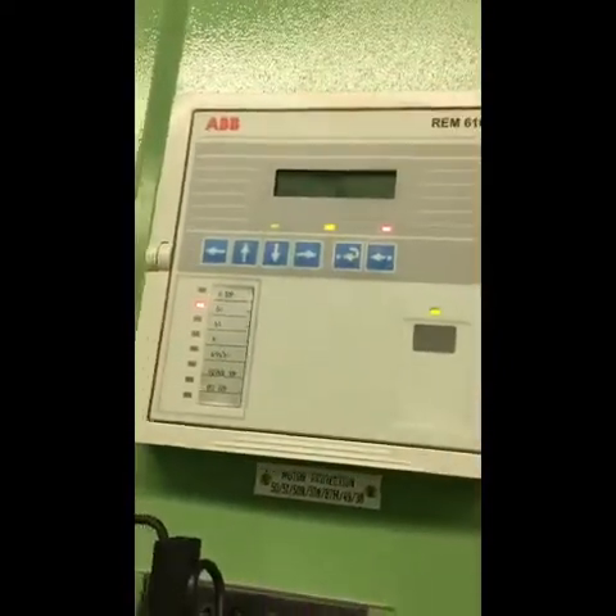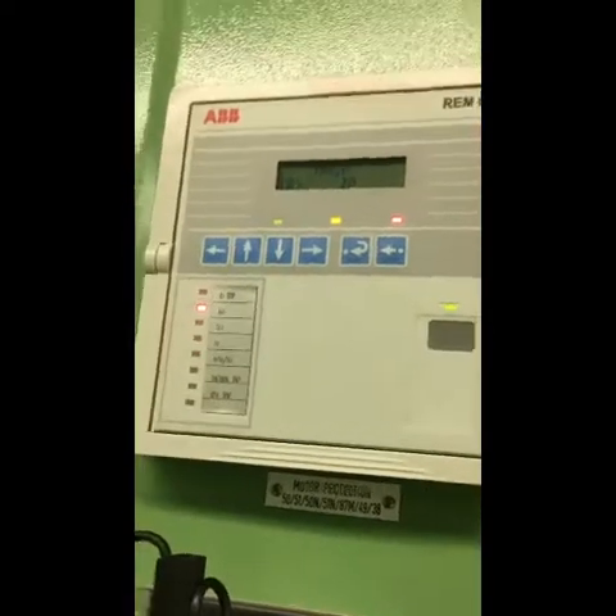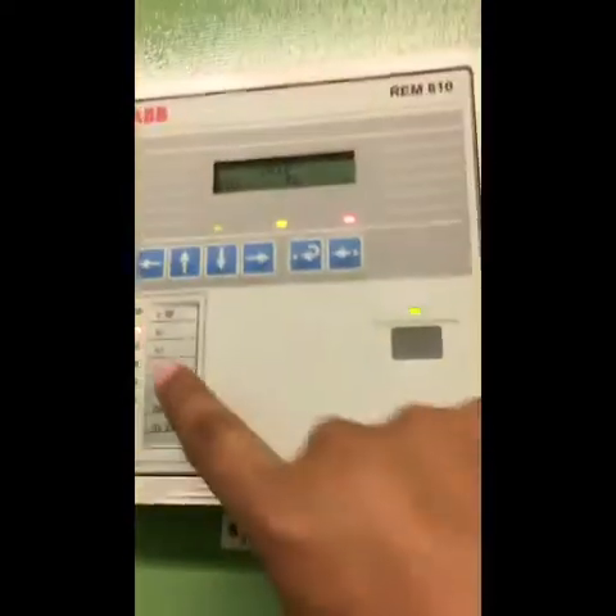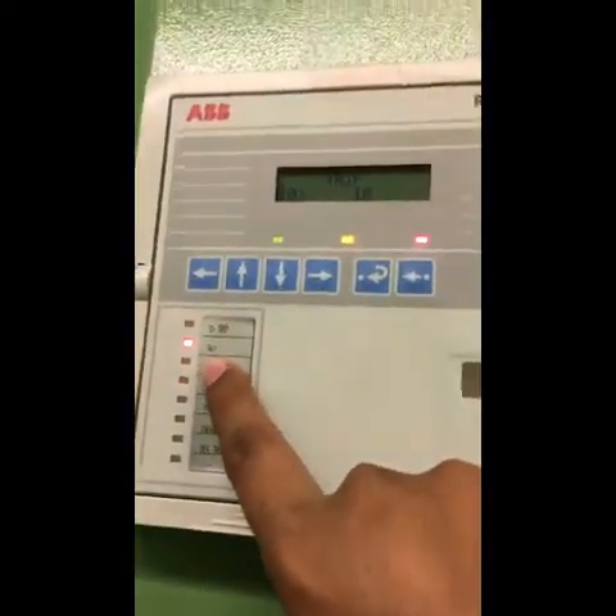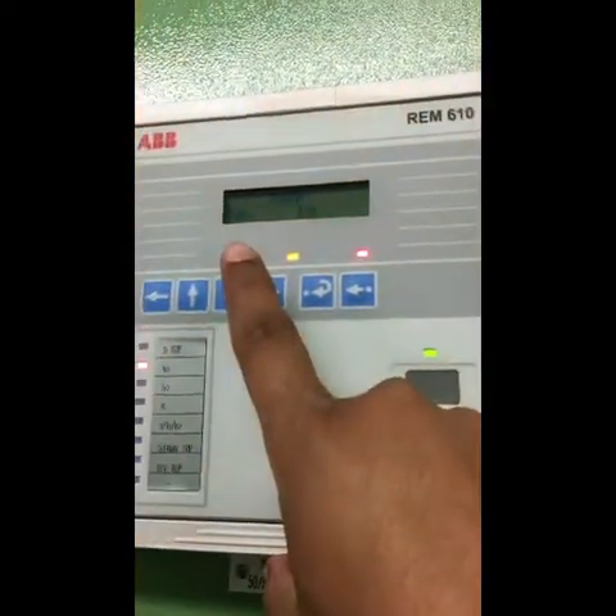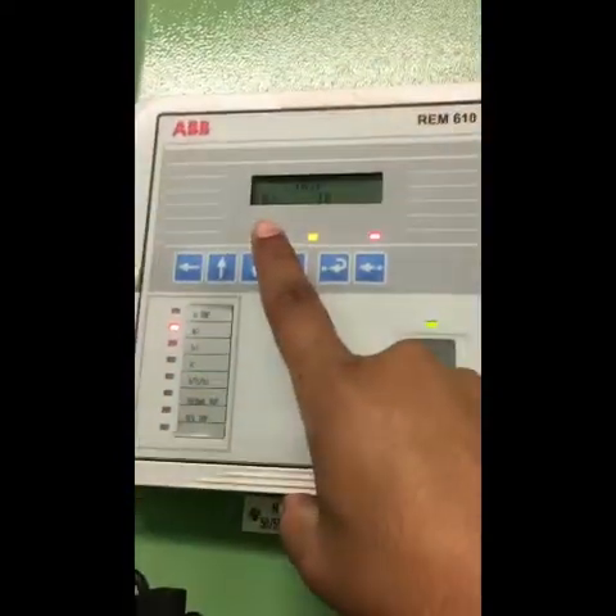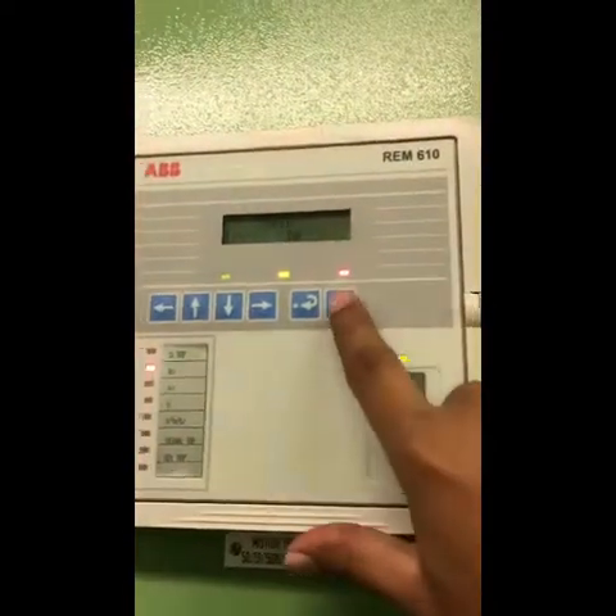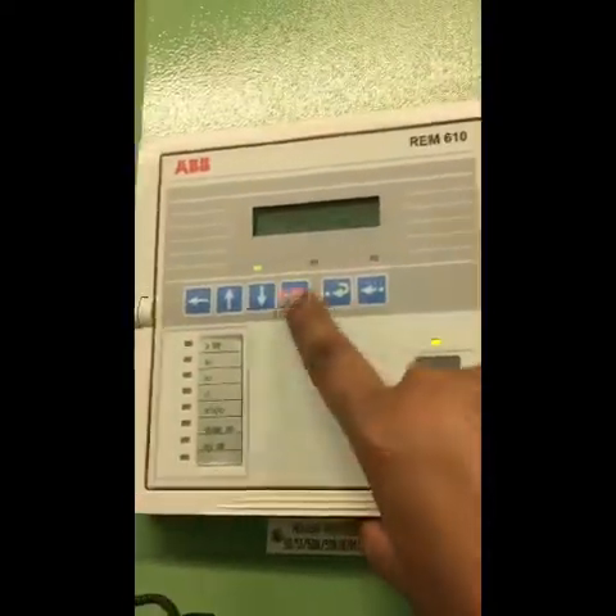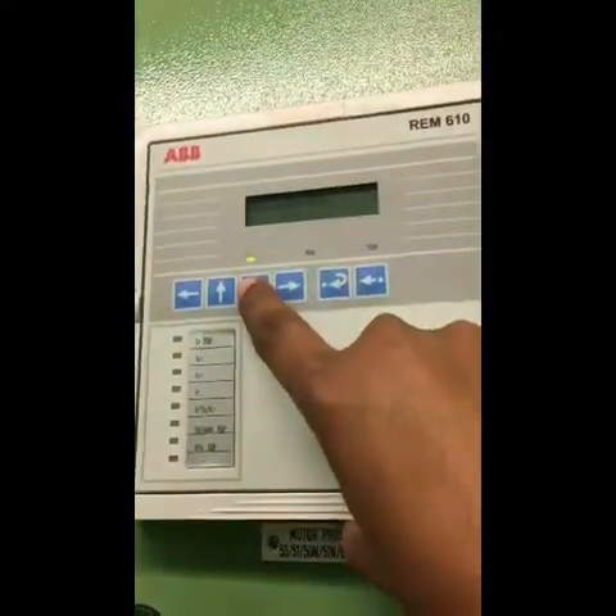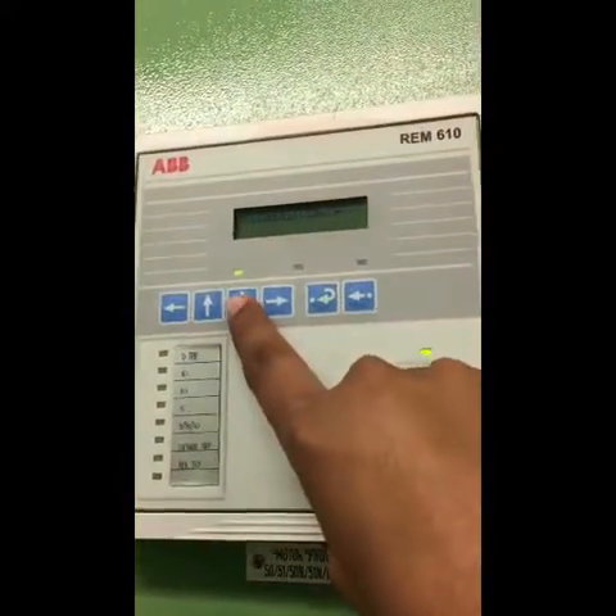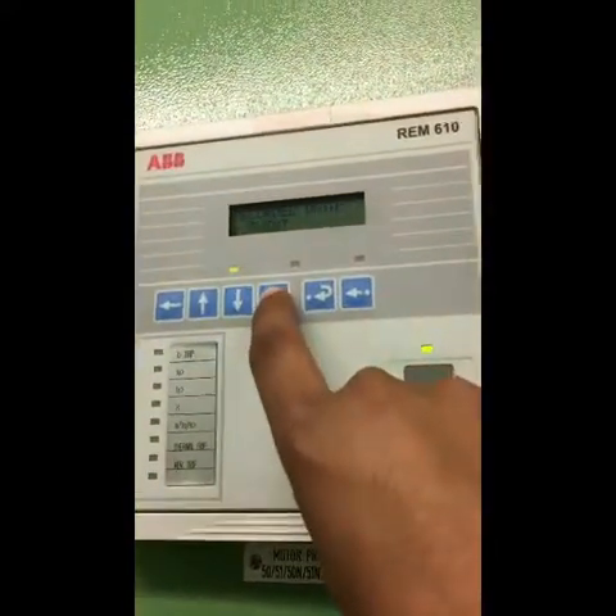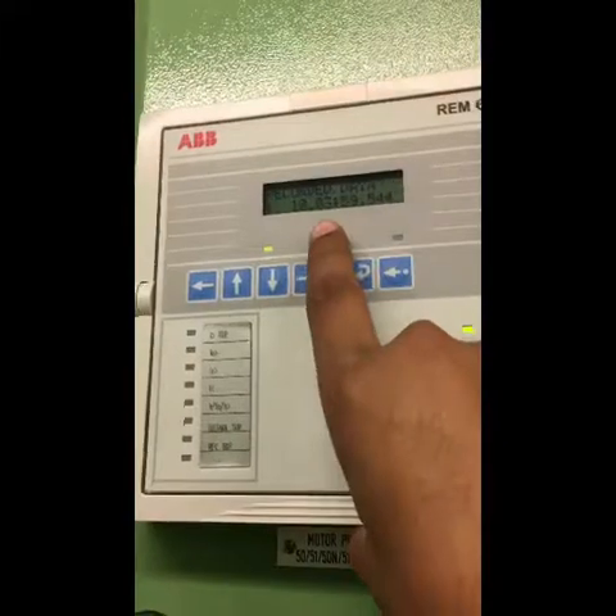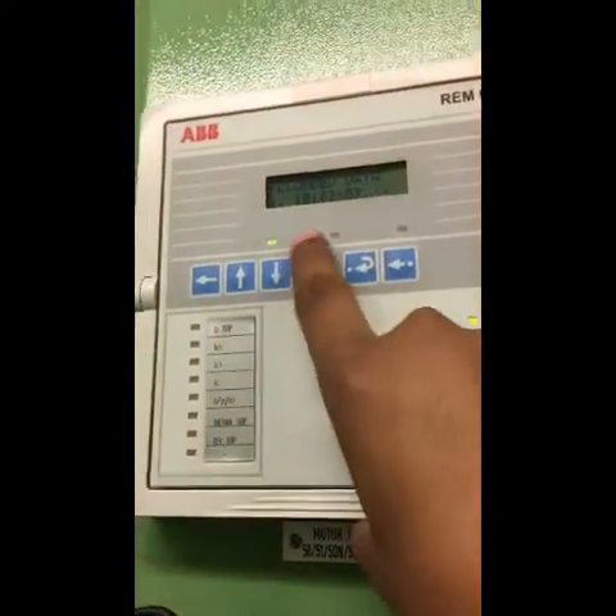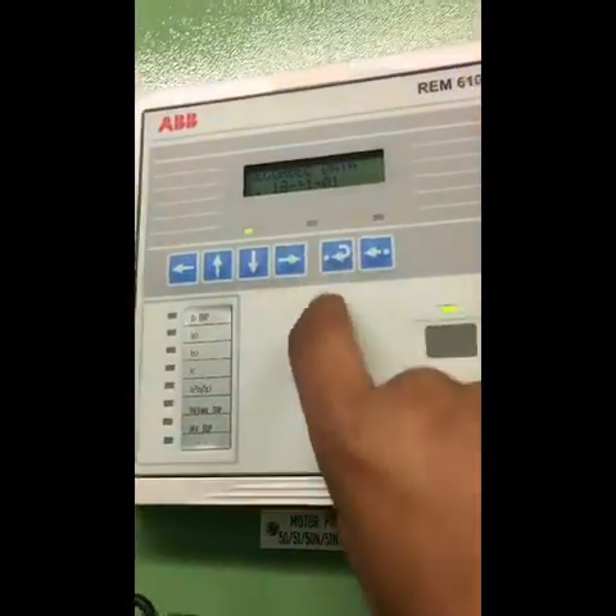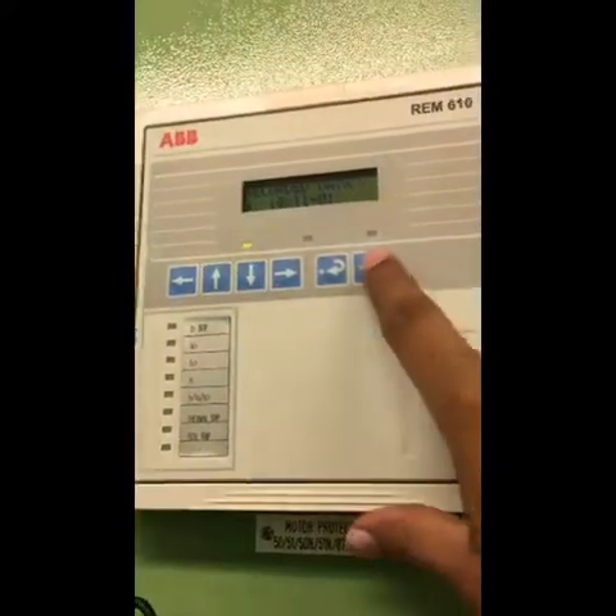Now this relay has tripped by earth fault. How do I know it is an earth fault? This LED indicated earth fault, and this is the symbol of earth fault, Io greater. I am going to reset to see the time of the earth fault happening. We will go to record the data, event, at 6 o'clock 3 seconds on the 1st of November 2018.